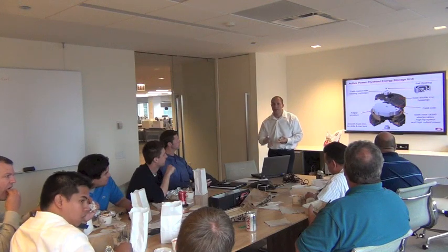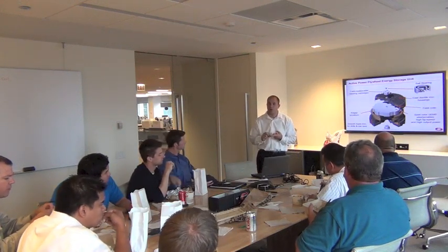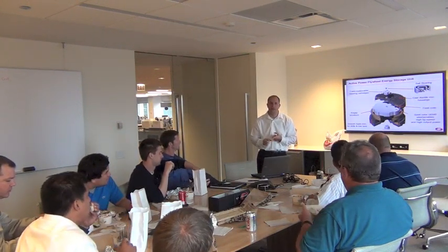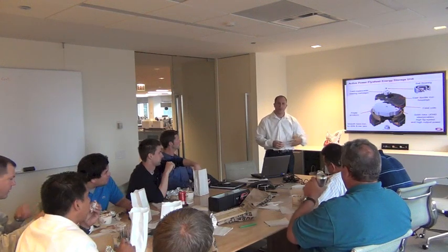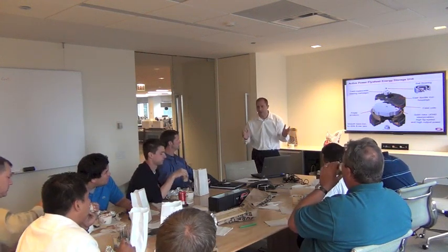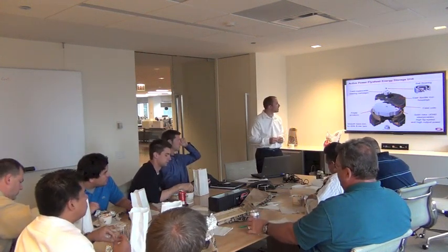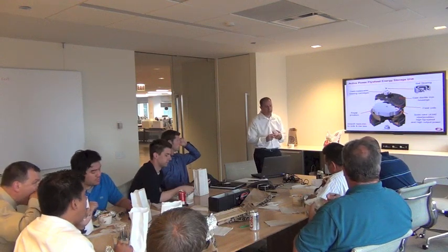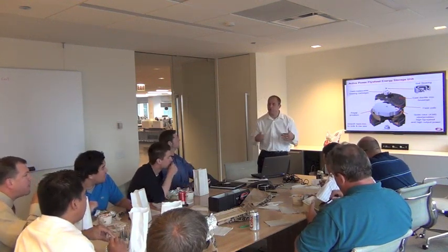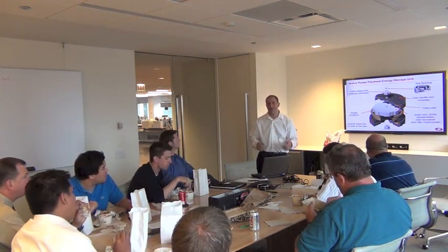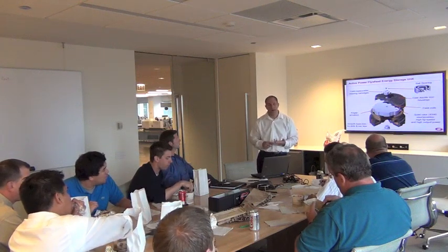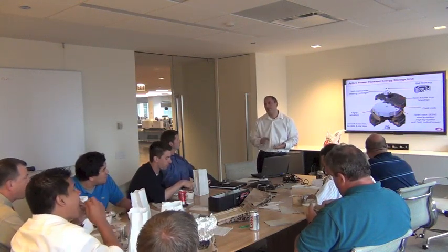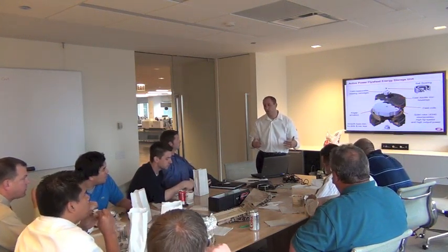The other maintenance items are there's oil in the vacuum pump that needs to be changed once a year, and it's a mineral oil, so it's easy to dispose of. It's not toxic or anything like that. The other maintenance item is there's filters on the front of the unit, depending on how dirty the environment is. Most data centers are pretty clean, but it just depends. But typically once a year, the filters are removable from the front.